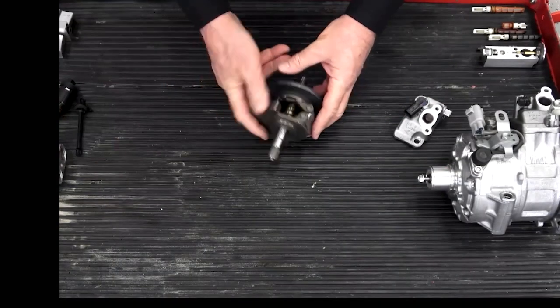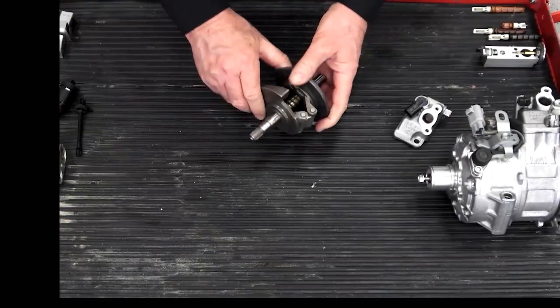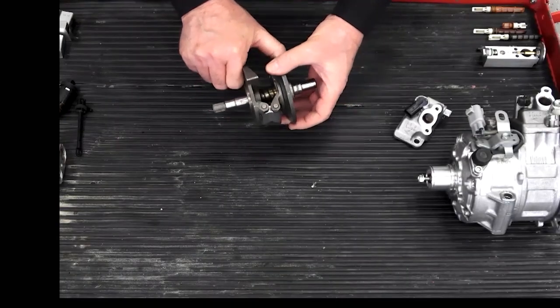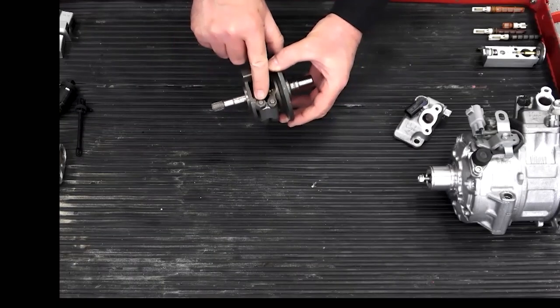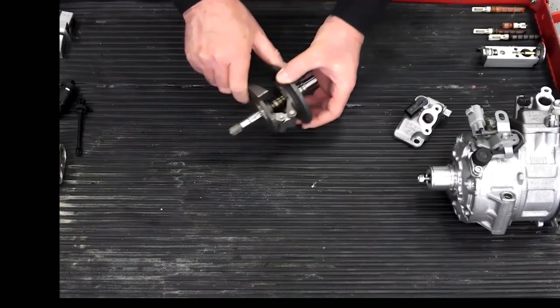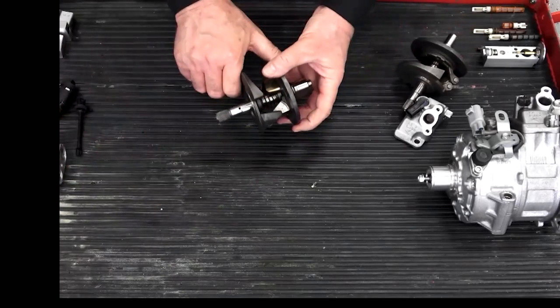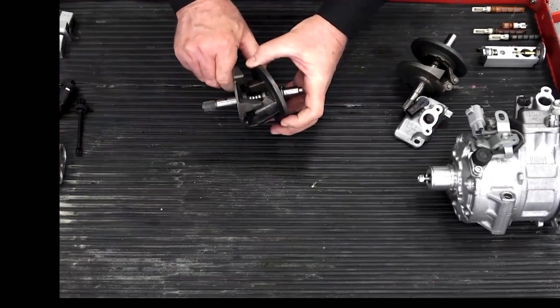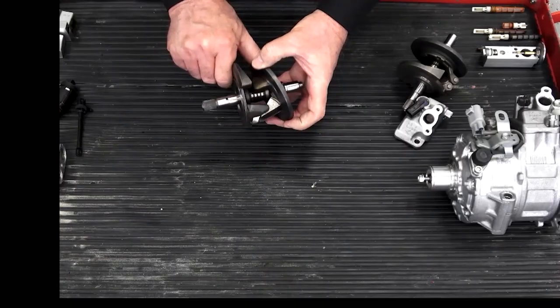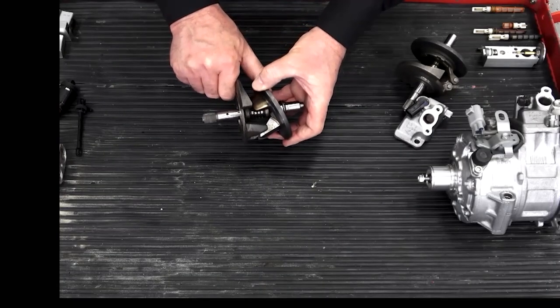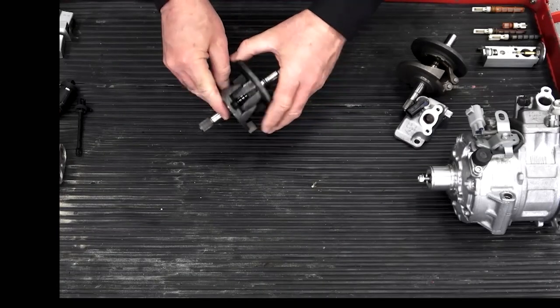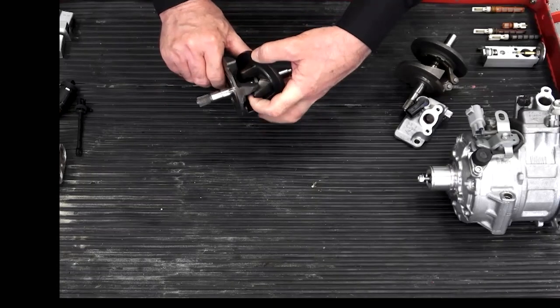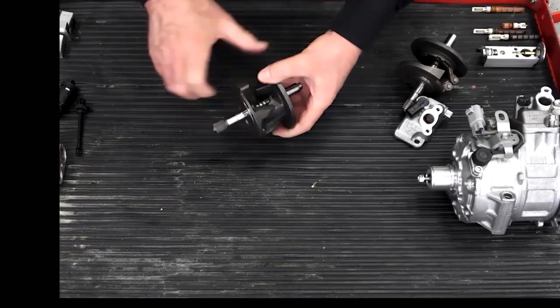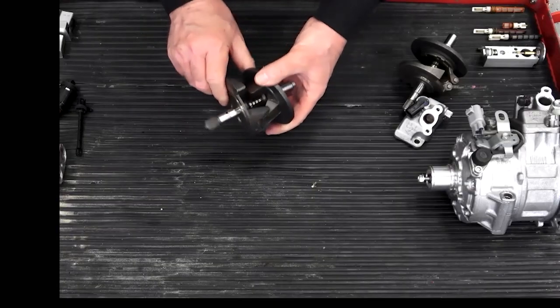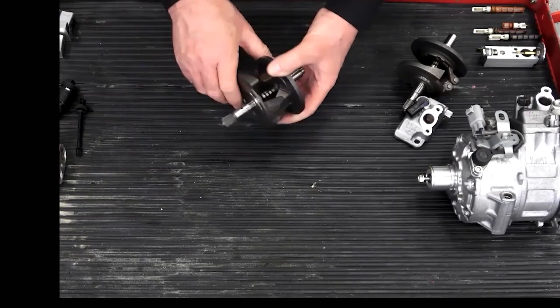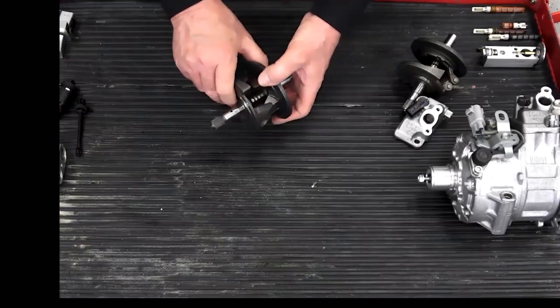So that's a quick review here. I will mention one other thing I see. This is a swash plate for one of these electronically controlled variable displacement compressors. Do you see that it's double hinged here, right here, like this? Well, here's one from an inexpensive compressor. If you could feel it in my hand, you may even be able to see it in the picture, it's got a very jumpy movement, and that's because it doesn't have double hinges. It's just got a sliding slot to control it. These are notorious for binding and sticking, and you get erratic operation. It doesn't get all the way to full displacement, and so on and so forth.